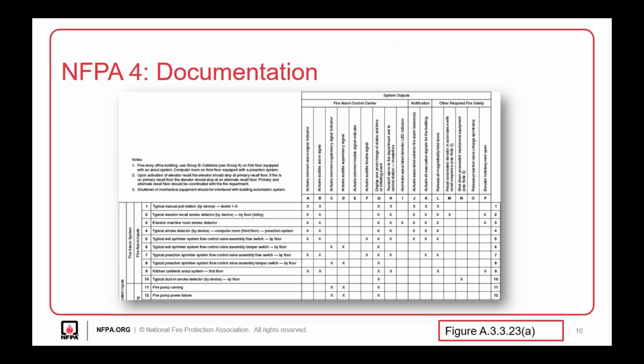Now I want to talk about documentation required for integrated system testing per NFPA 4. Before that, one thing to note: we're not making documentation just for the sake of it. Documenting the results of these tests and the means and methods for executing them is crucial to the building's future. As discussed, buildings that undergo an initial integrated system test typically have an integrated system test plan for either a periodic test that comes up or a trigger-based integrated system test.